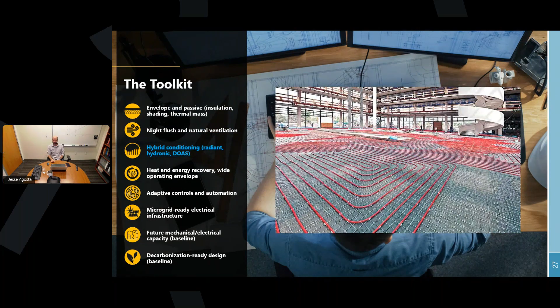The key is that the dedicated outside air system on the roof be sized for an increasing outside air temperature, not just with dry bulb temperatures, but also with wet bulb and relative humidity. If our insulation is good and we have great thermal mass, then we can rely entirely on our DOAS system to remove all of that latent energy that's being added to the system due to the increase in temperature of our climate. So moving on now to our next strategy, which is energy recovery.